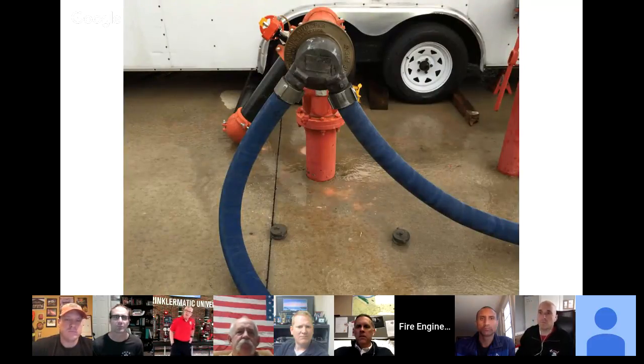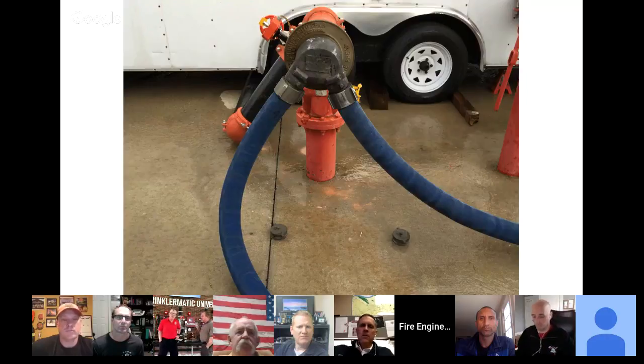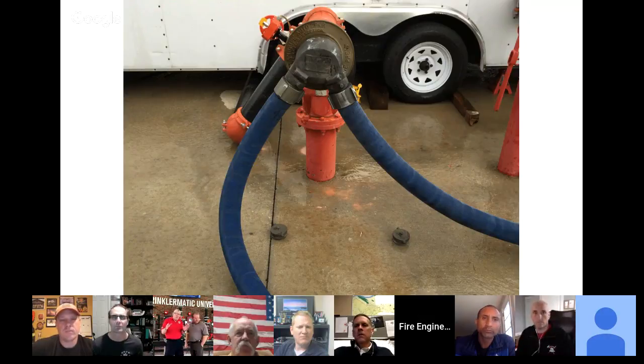There we go. They plumbed a fire department connection into this trailer, which was really neat because the pressure gauge on the pump and the pressure gauge on the apparatus were just a few steps from each other, so you could see them competing with the fire pump. There can only be one source of water for a fire suppression system, either the fire pump or the fire apparatus pump at the FDC, whichever has the higher pressure.